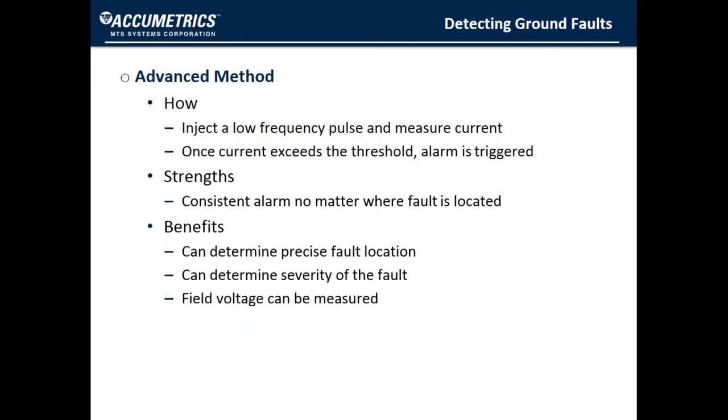This method provides both the location of the fault and the fault severity. We also measure field voltage, which is typically unavailable on a brushless exciter, and that is another useful piece of information that comes along with this kind of detector.